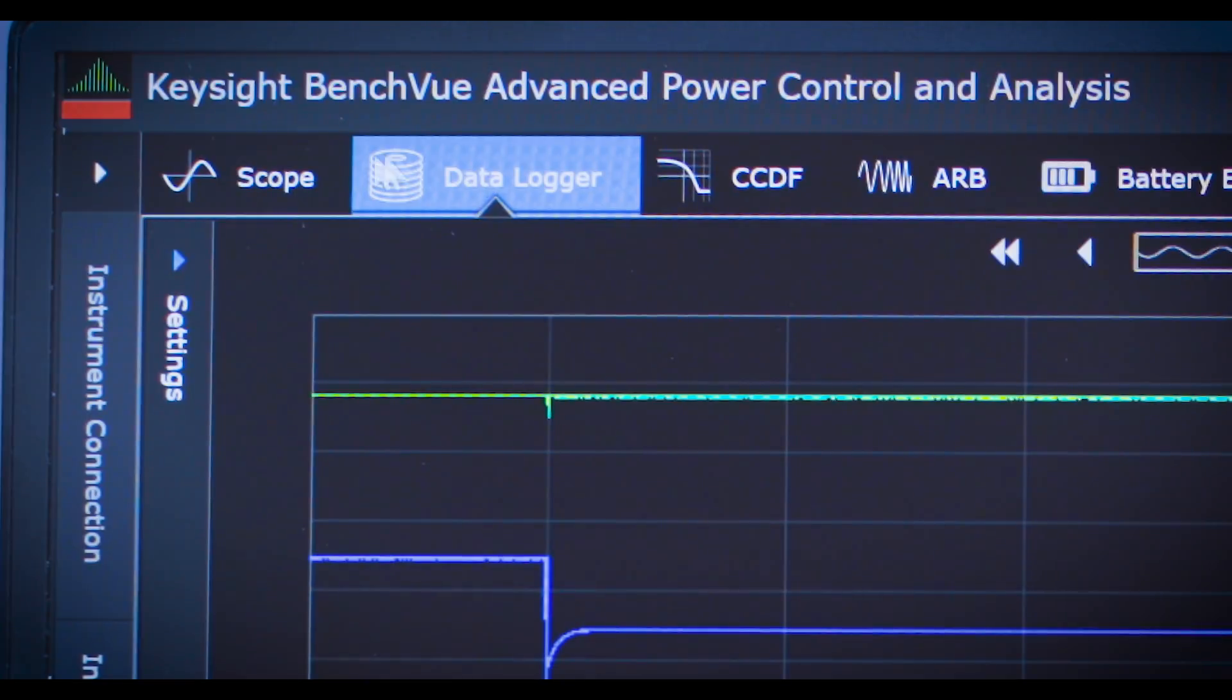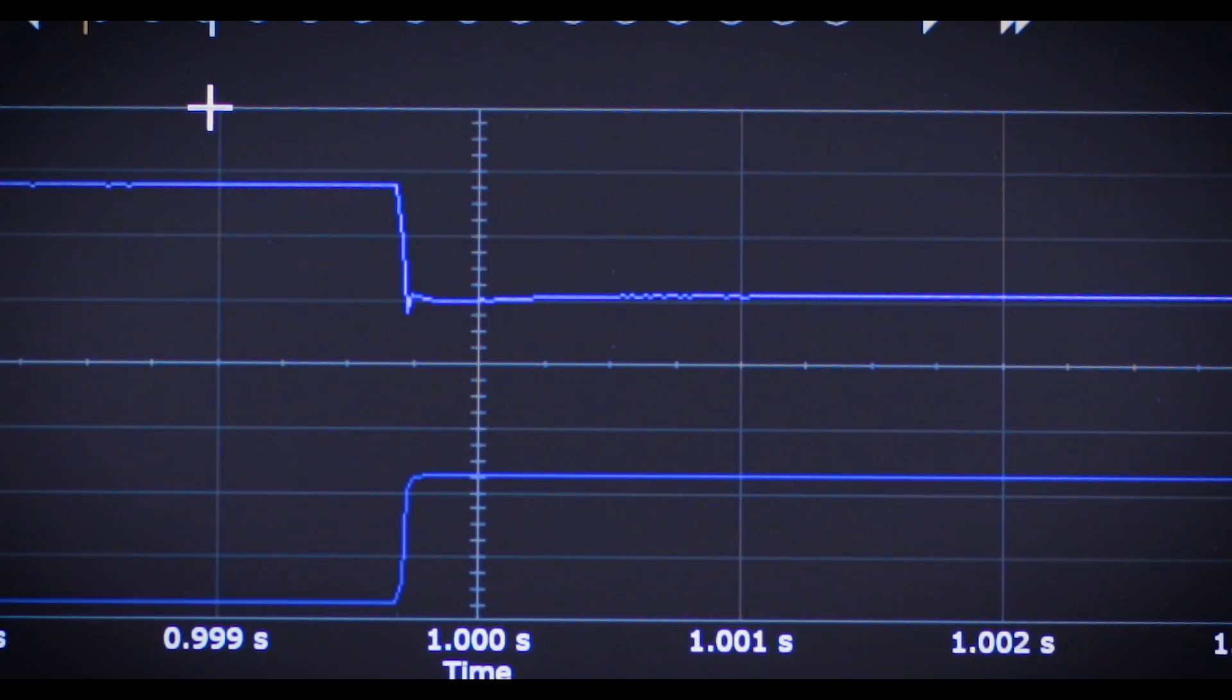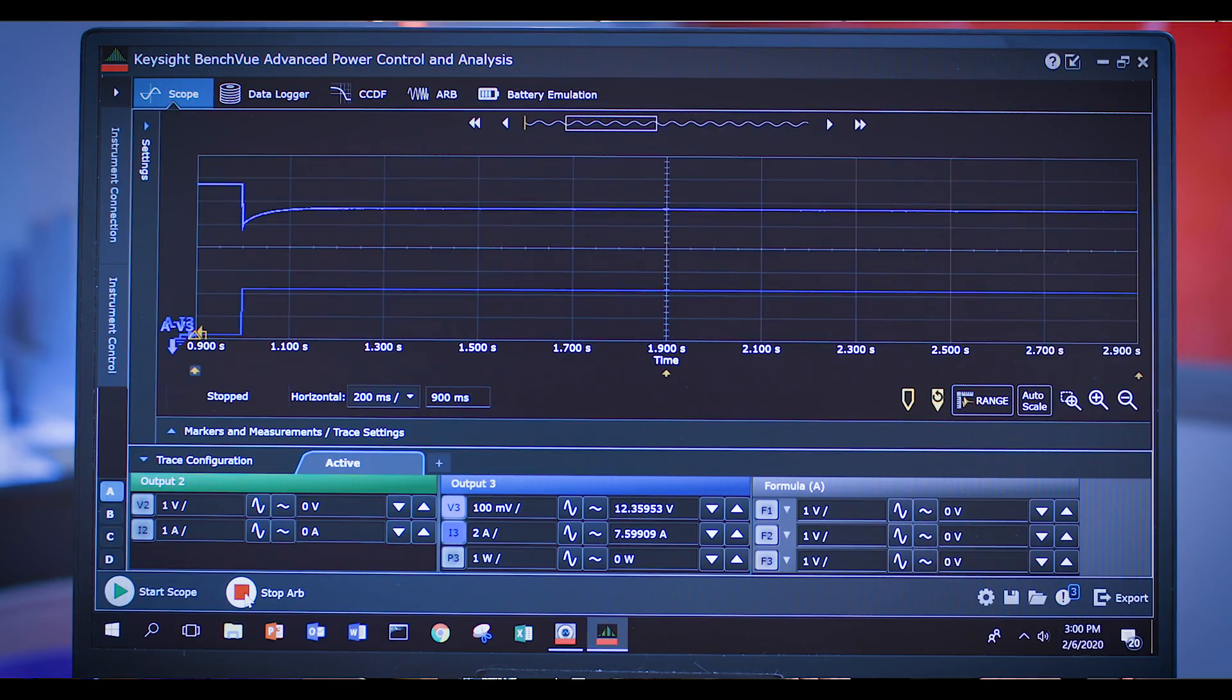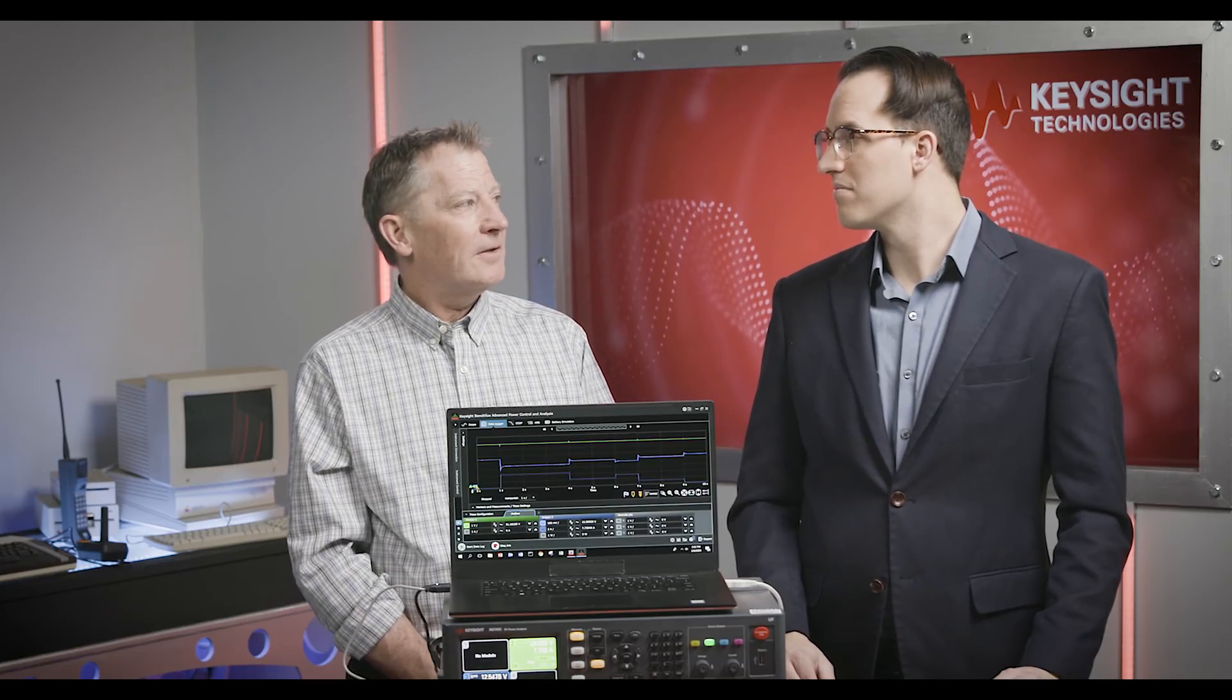This power analyzer also has a scope capability, so you can trigger and zoom in on short events like an edge and peek into your system without having to pull out a separate scope. You can also level trigger and have it do something when the trigger occurs. One of the most common things is to have the outputs turn off based on the level trigger. This could really save things if your test goes south—if something shorts out and your current spikes, you can shut everything down. Instead of setting the output to zero volts, you can just turn off the output as the voltage heads to zero.